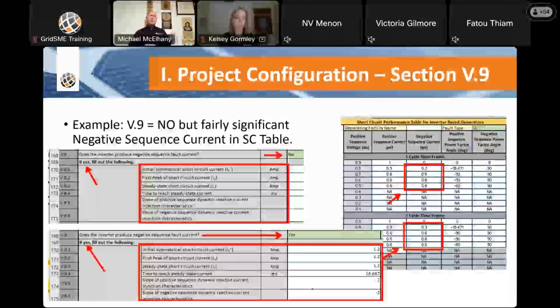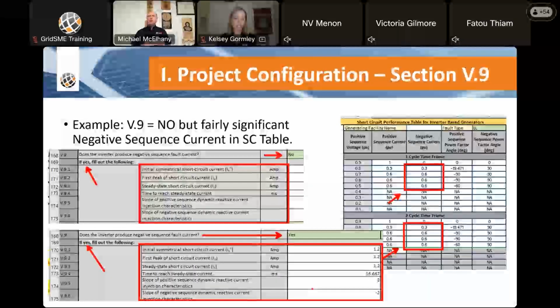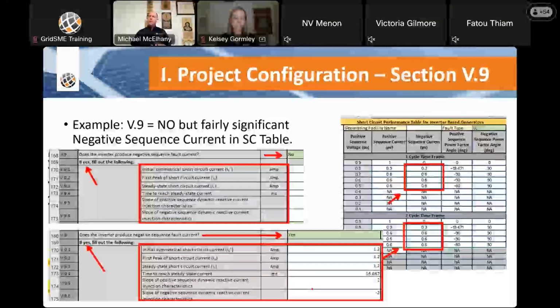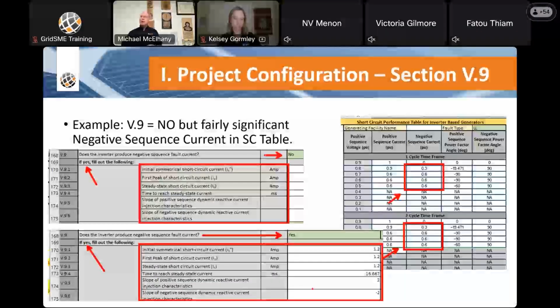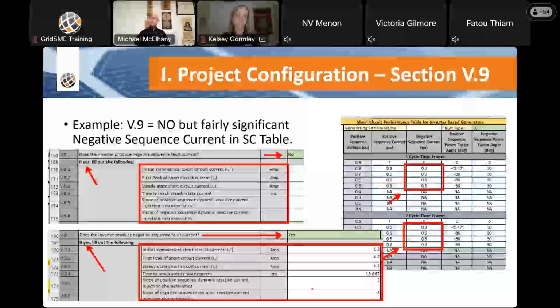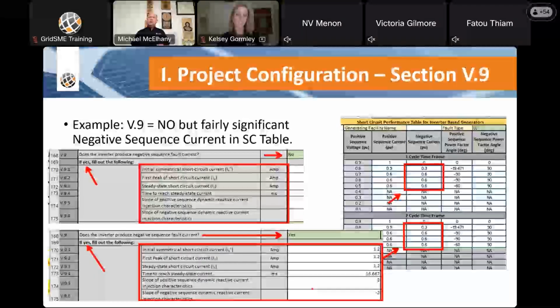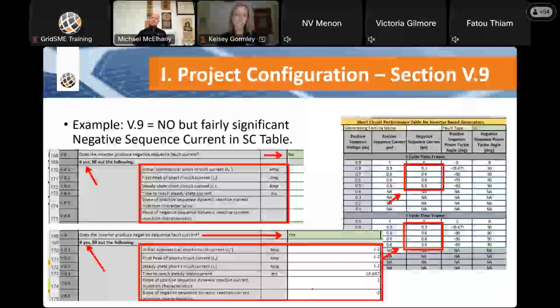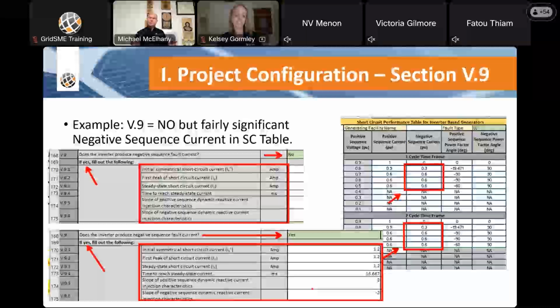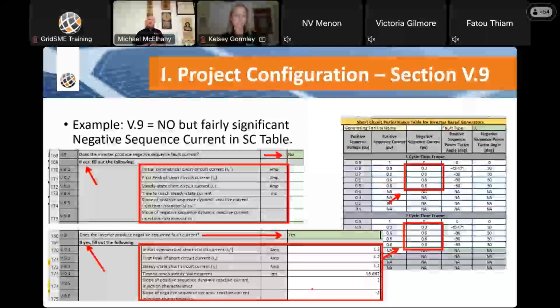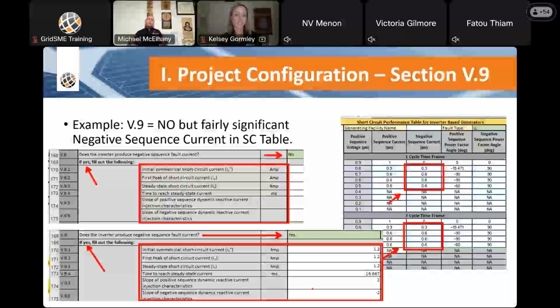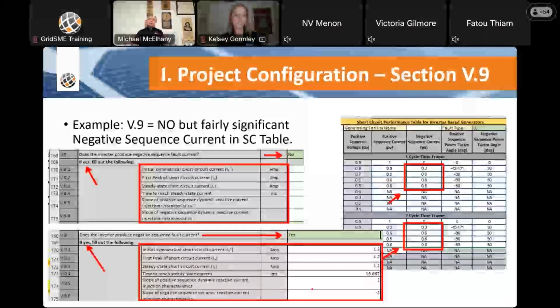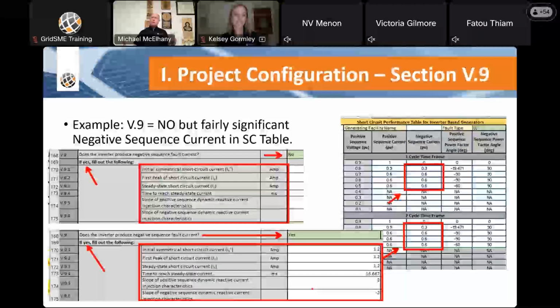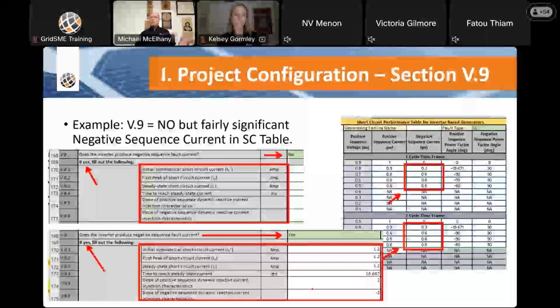Does the inverter produce negative sequence fault current? No, under a balanced three-phase fault, but yes, under another fault condition. So how do you answer the question? Yes and no. And when you answer yes, then you have to fill out the following V.9.1 through .6 that contains this additional information. And then if you do say yes, CAISO wants to know, what's the prioritization of negative sequence versus positive sequence current?